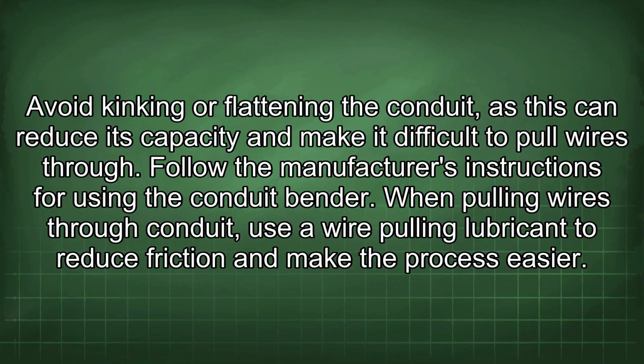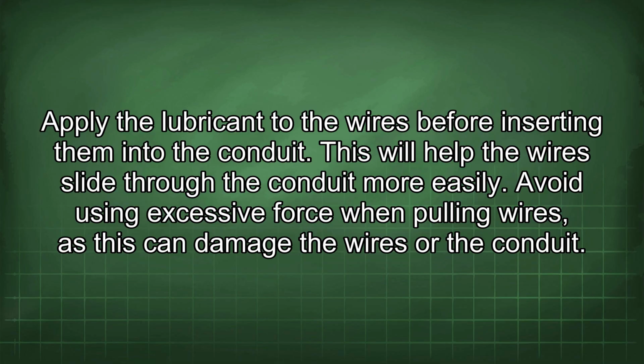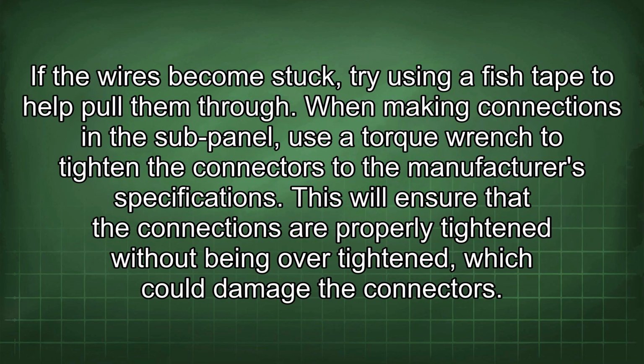When pulling wires through conduit, use a wire pulling lubricant to reduce friction and make the process easier. Apply the lubricant to the wires before inserting them into the conduit. This will help the wires slide through the conduit more easily. Avoid using excessive force when pulling wires, as this can damage the wires or the conduit. If the wires become stuck, try using a fish tape to help pull them through.